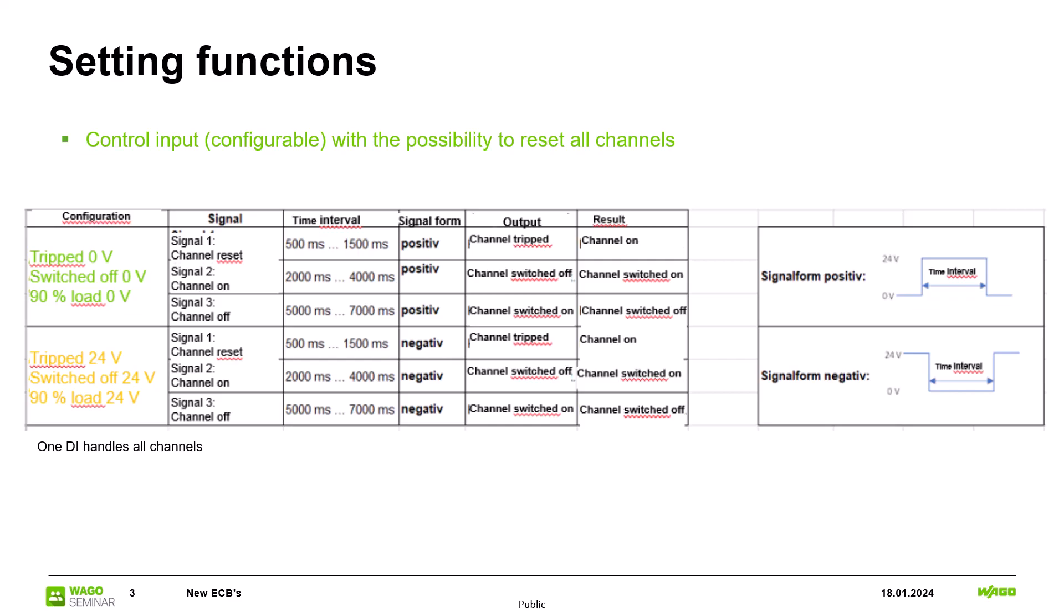The shape of this input signal depends on the signal output setting. The output switches from 24 to 0V as a factory setting. If you use this you need a 24V signal at the signal input. If you set the signal output change from 0 to 24V you need a 0V signal on the signal input.